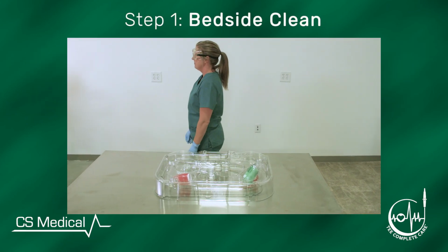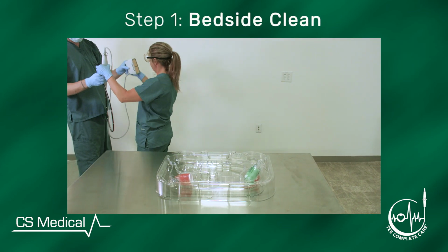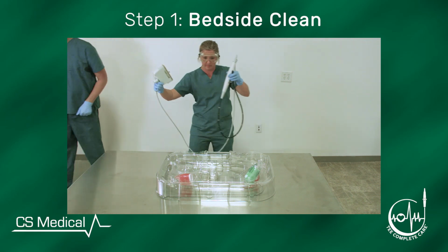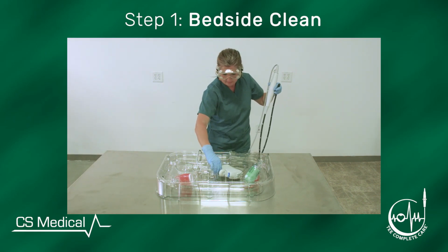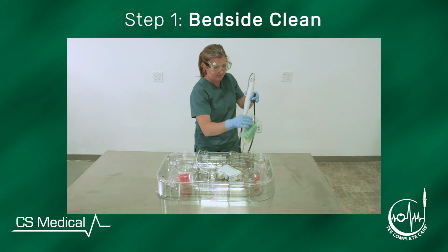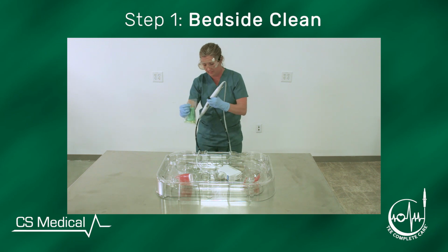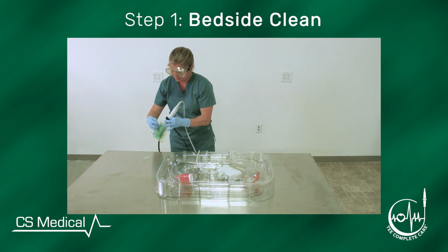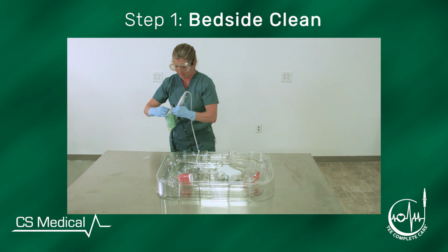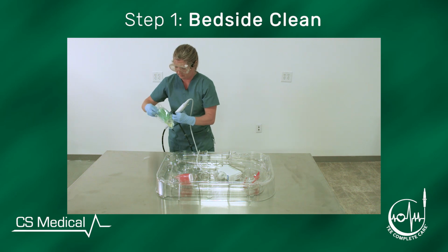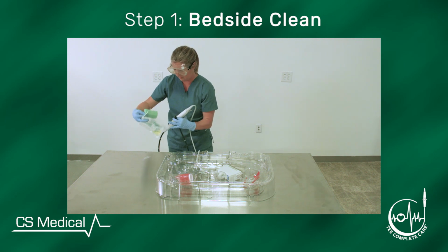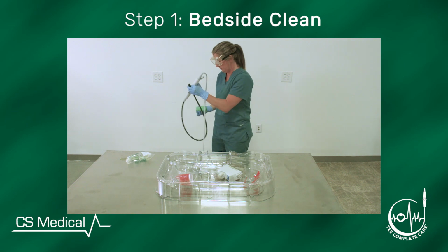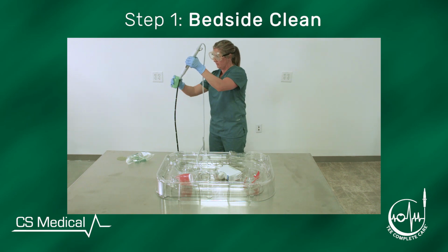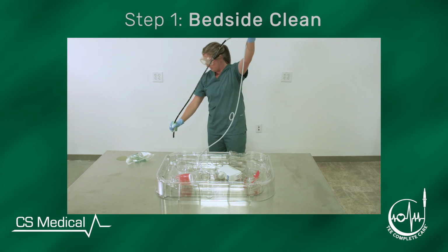Step 1. Bedside clean the soiled TEE probe as soon as possible, once removed from the patient's esophagus. T-Zyme enzymatic sponges provide a simple and effective method for enzymatic application to the TEE probe insertion shaft directly after removal from the patient's esophagus. T-Zyme sponges are pre-saturated with an enzymatic to begin the process of breaking down bioburden.